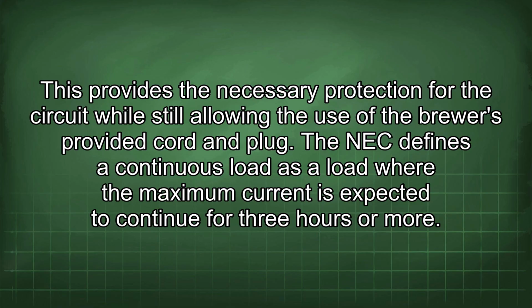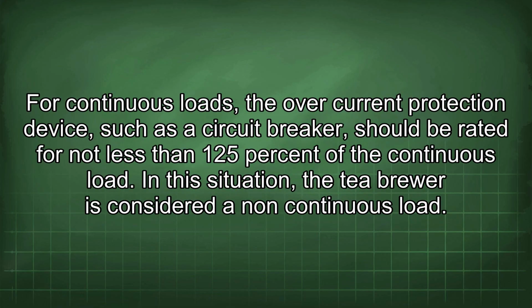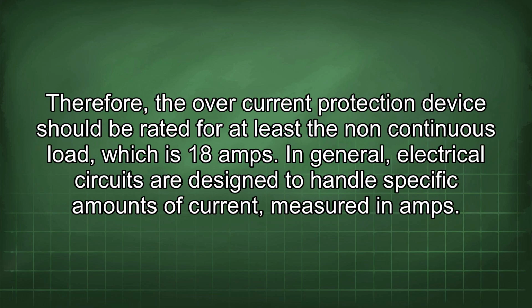The NEC defines a continuous load as a load where the maximum current is expected to continue for 3 hours or more. For continuous loads, the overcurrent protection device, such as a circuit breaker, should be rated for not less than 125% of the continuous load. In this situation, the tea brewer is considered a non-continuous load. Therefore, the overcurrent protection device should be rated for at least the non-continuous load, which is 18 amps.